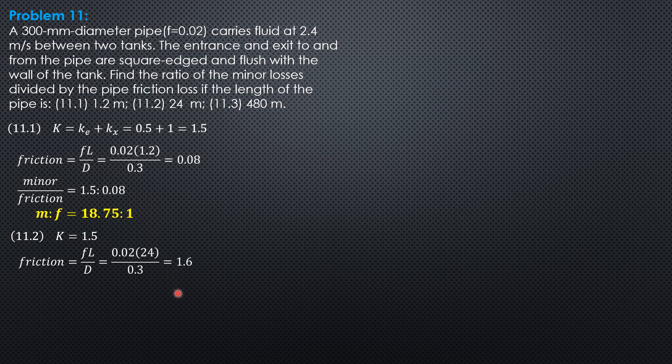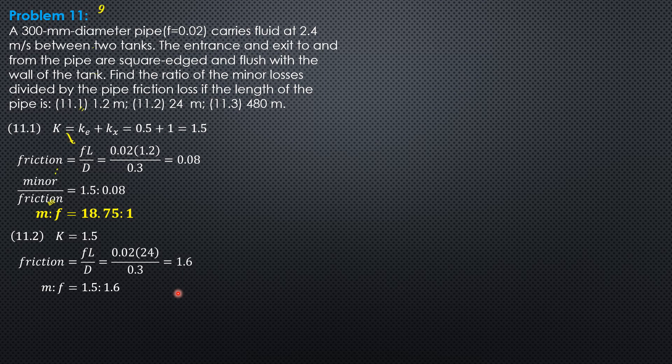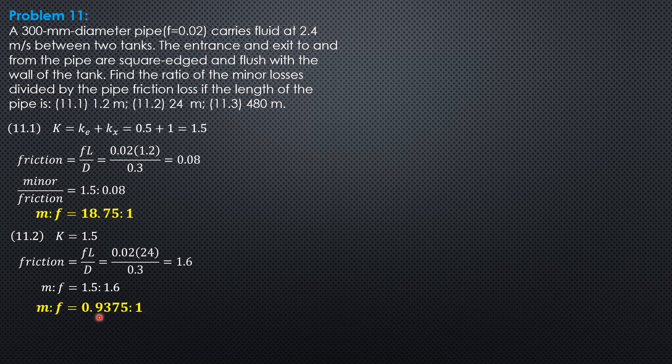That would be 1.6, so ratio of minor to friction is 1.5 as to 1.6. So 1.5 divided by 1.6 is 0.9375 as to 1. This time they are almost the same, but the major loss is now greater, or frictional loss is now greater.